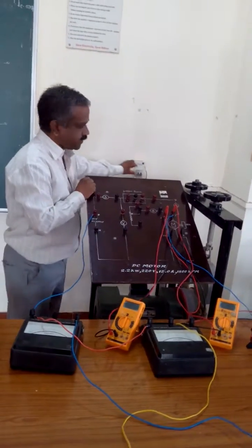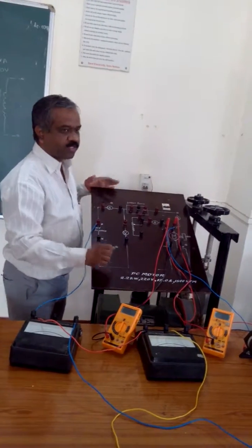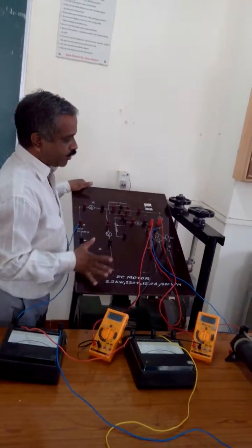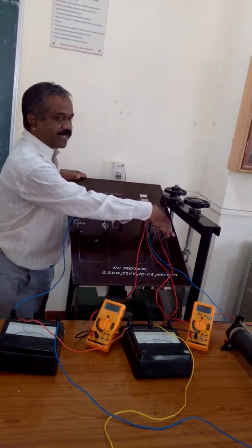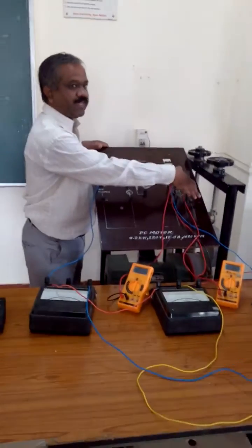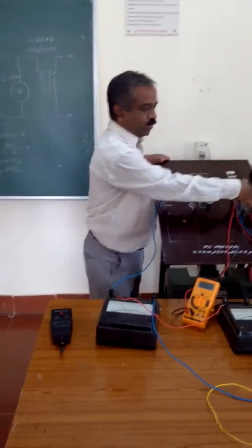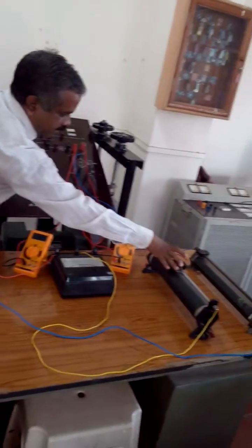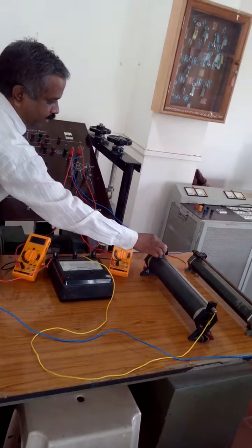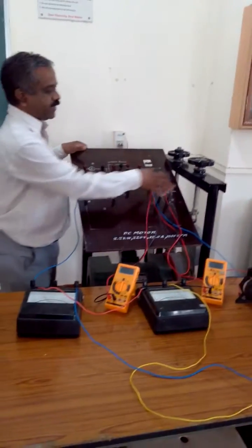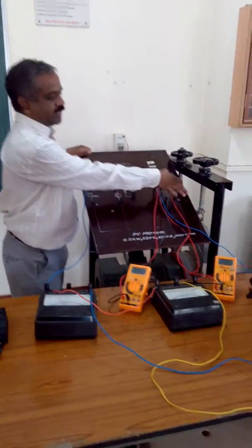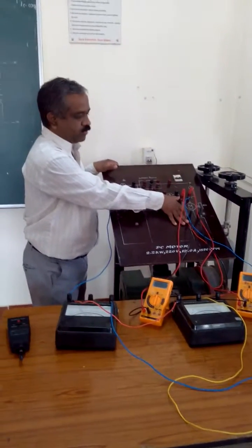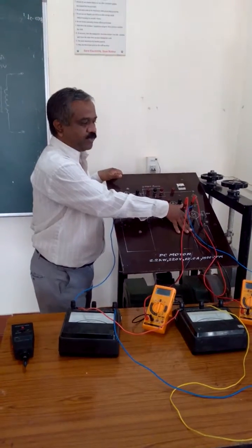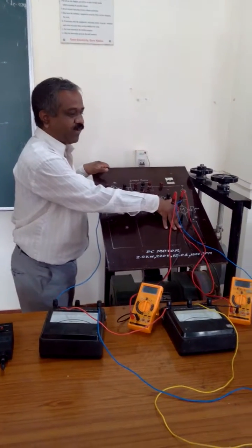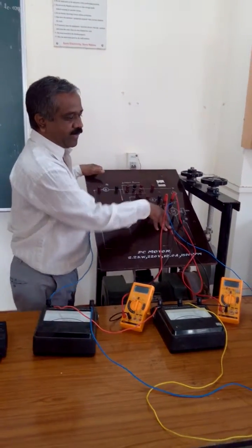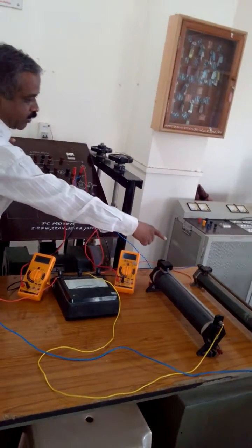So I will start the connection. Always remember, your motor should start at low speed. As you know, speed is directly proportional to armature voltage, which means I should keep less voltage at start, so the armature voltage should be low. This rheostat should be at the maximum position so that more voltage drops across the rheostat and less voltage drops across the motor armature. Field current should be maximum, because field current, or flux, is inversely proportional to speed. So I will keep the field rheostat at the 0 position. This is the 0 position for the rheostat.